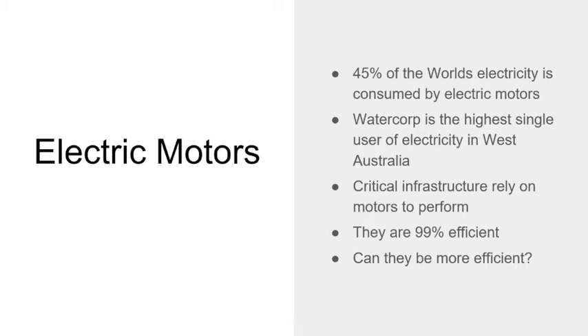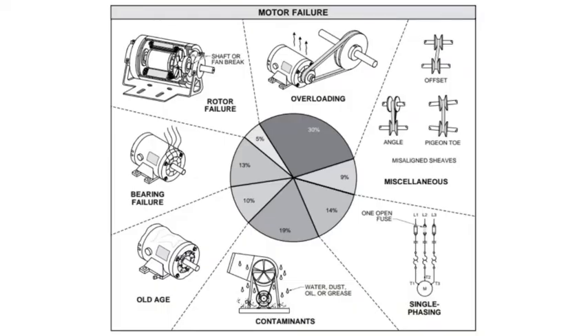I go back to my earlier slide where it talks about how much the world could save by improving efficiency of motors. There's not a lot you can do to something that's really quite good, and there is always room for improvement, but it's all about the load - what power goes into a motor and what comes out the other end. So the things that cause motors to fail are typically overloading. On this graph here, you can look at a nameplate on a motor and it'll tell you exactly what it wants from the supply in volts and frequency and so on, and it'll tell you what it'll give you in RPM on the output. They don't vary unless you vary them yourself.